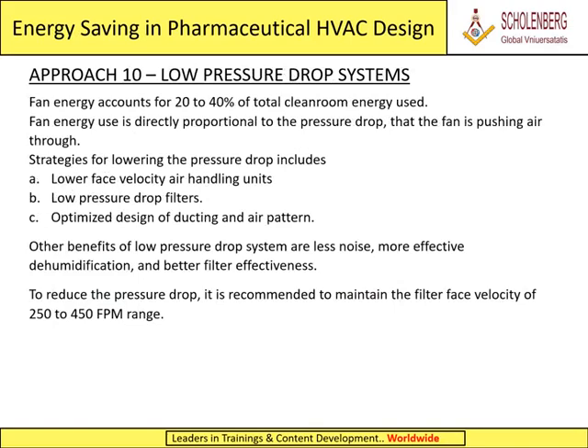Approach 10, Low pressure drop systems. Fan energy accounts for 20 to 40% of total clean room energy used. Fan energy use is directly proportional to the pressure drop that the fan is pushing air through. Strategies for lowering the pressure drop include: A. Lower face velocity air handling units. B. Low pressure drop filters. C. Optimized design of ducting and air pattern. Other benefits of low pressure drop system are less noise, more effective dehumidification, and better filter effectiveness. To reduce the pressure drop, it is recommended to maintain the filter face velocity of 250 to 450 fpm range.